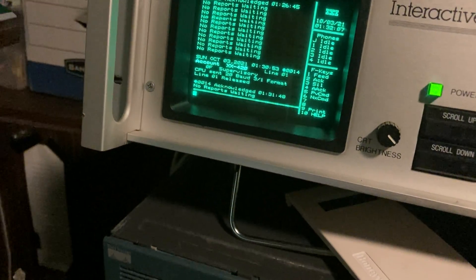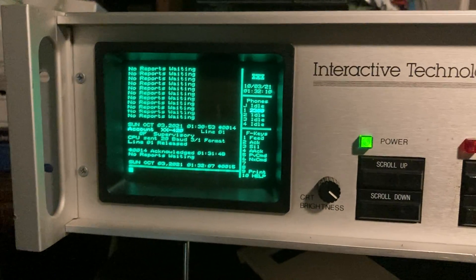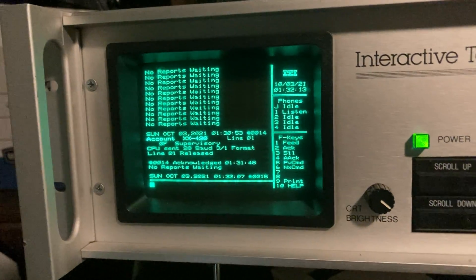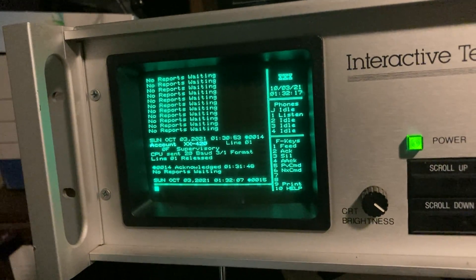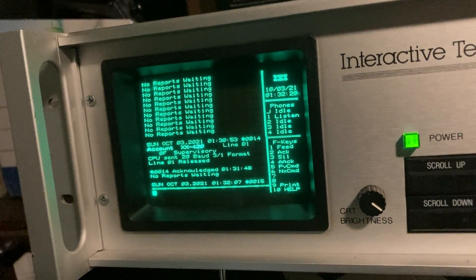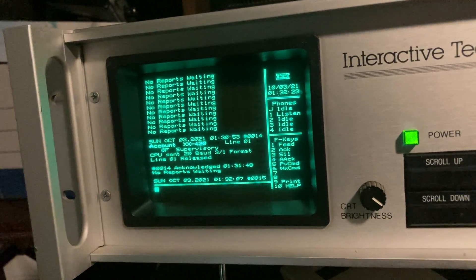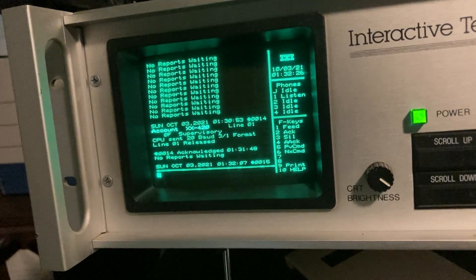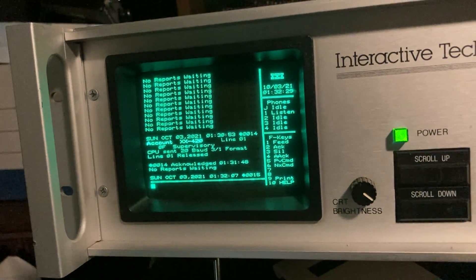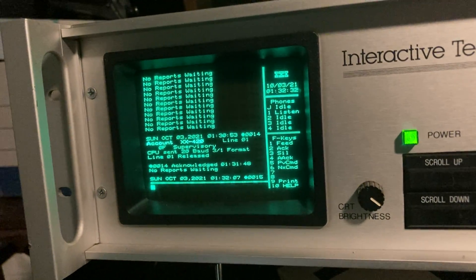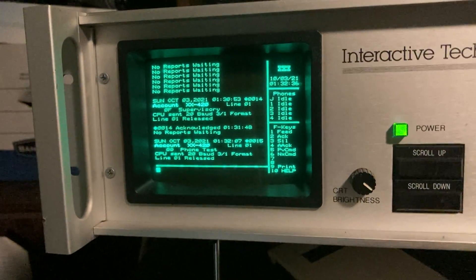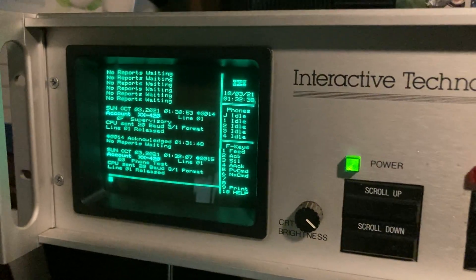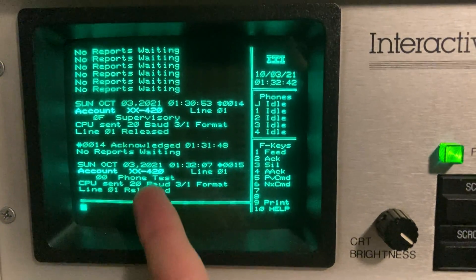And this receiver is kind of nice because you can actually specify what your report codes show up as. So on the Radionics one I can't have zero show up as a test, but I always use zero as my test report code. This one you can change that. It's typically for 3 plus 1 format it was zero through nine is an alarm, B is an opening report, C is a closing report, D is cancel report or alarm cancel, E is a trouble restoral and F is a trouble.